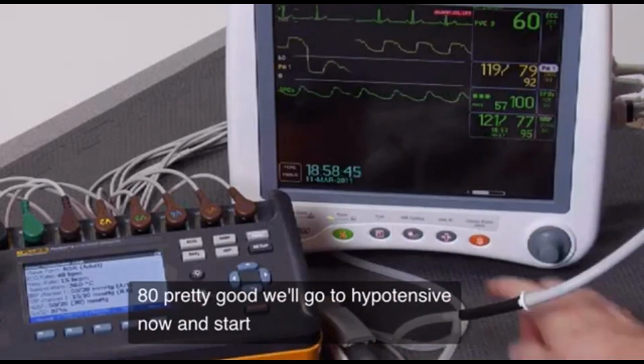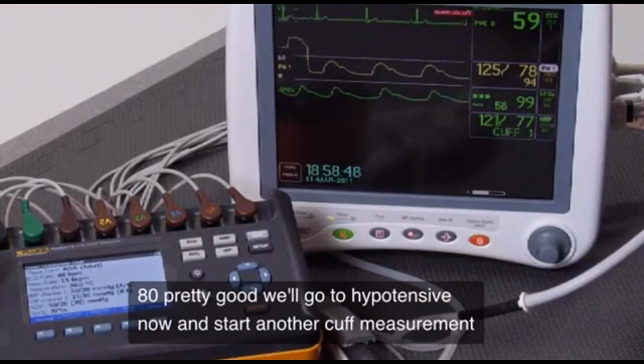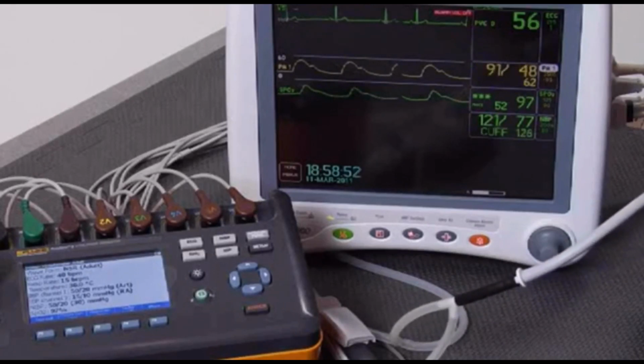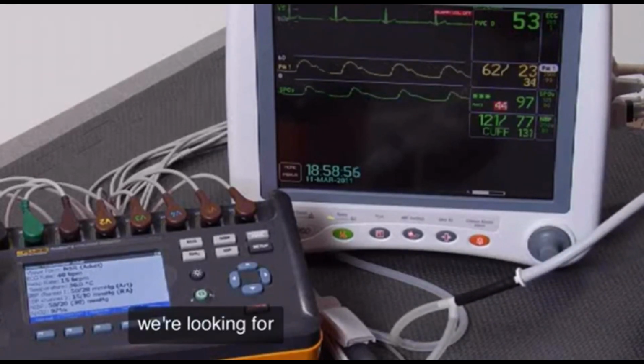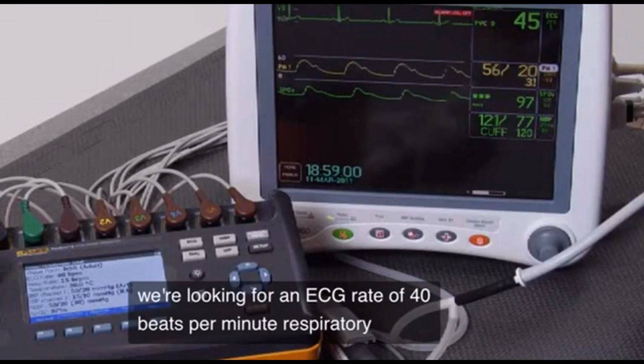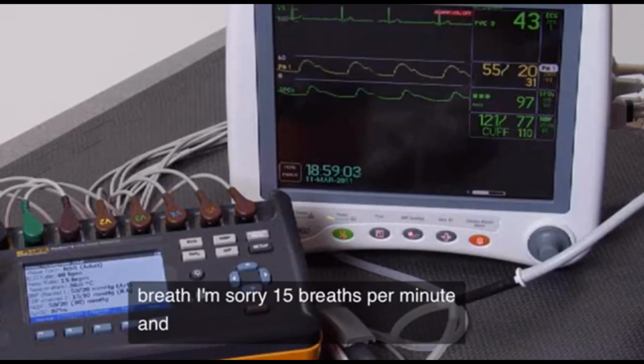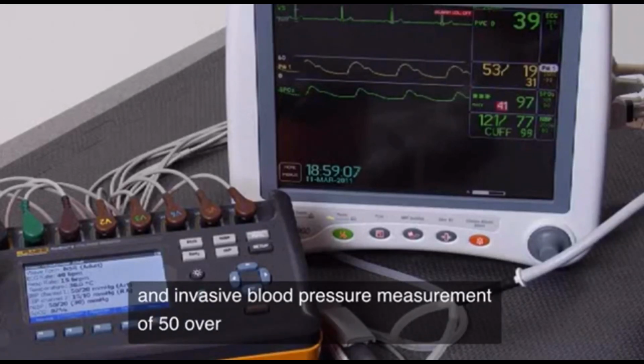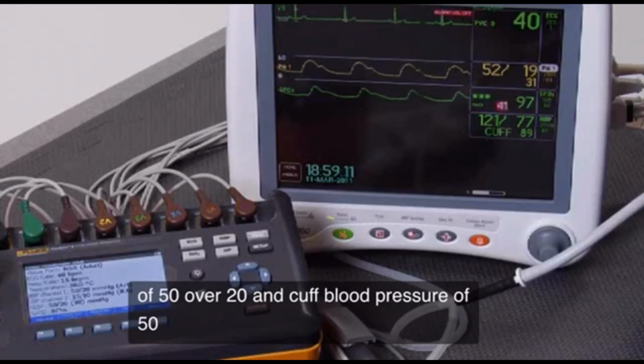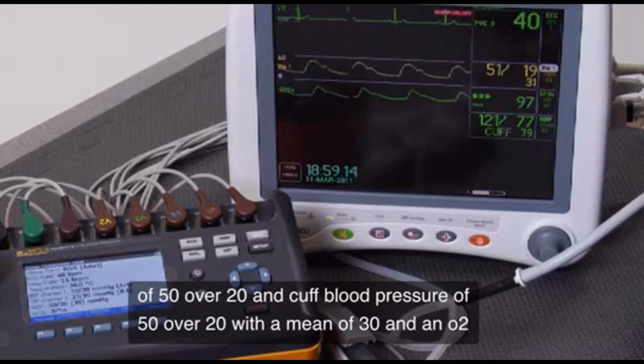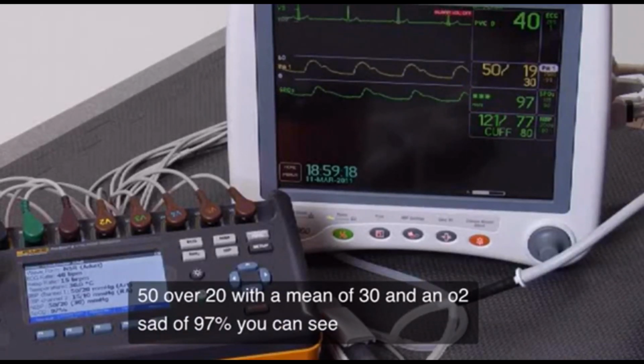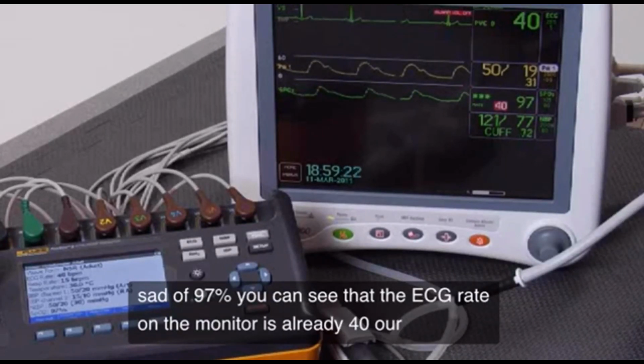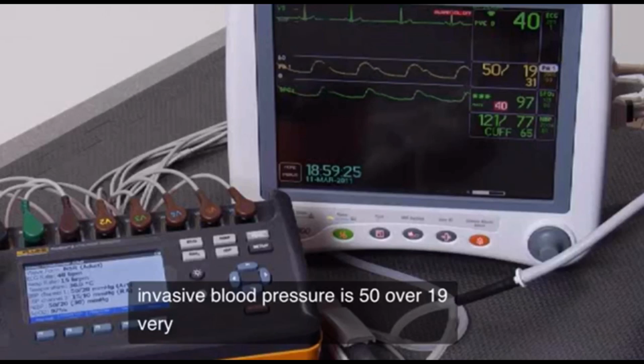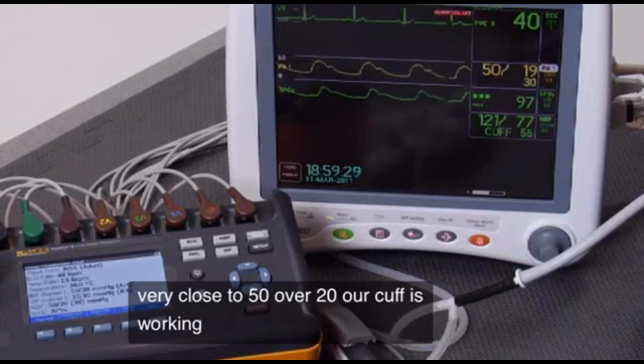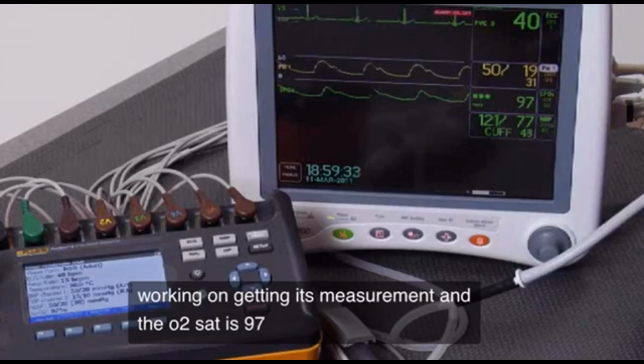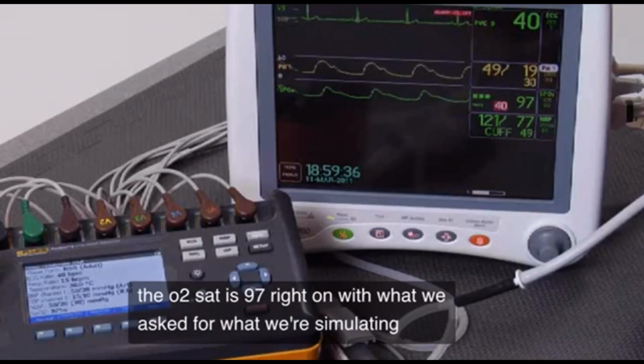We'll go to hypotensive now and start another cuff measurement. We're looking for an ECG rate of 40 beats per minute, respiratory rate of 15 breaths per minute, and invasive blood pressure measurement of 50 over 20, and cuff blood pressure of 50 over 20 with a mean of 30, and an O2 sat of 97%. You can see that the ECG rate on the monitor is already 40. Our invasive blood pressure is 50 over 19, very close to 50 over 20. Our cuff is working on getting its measurement, and the O2 sat is 97, right on with what we asked for, what we're simulating.